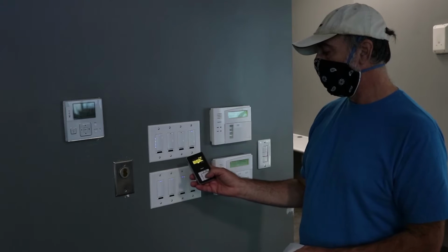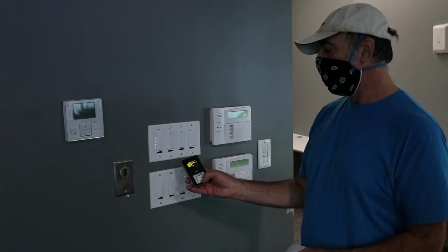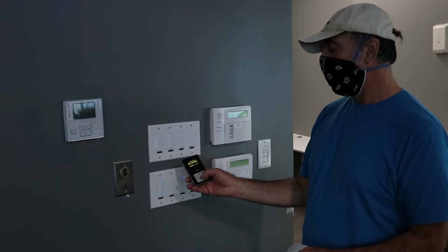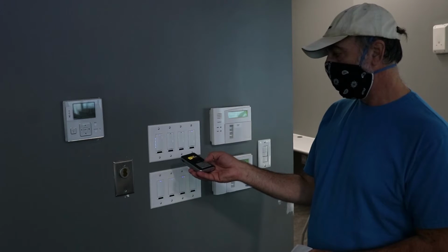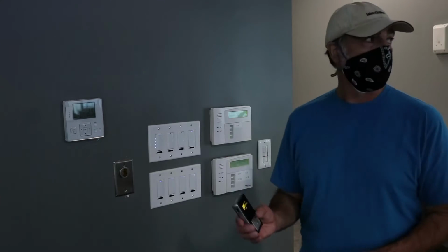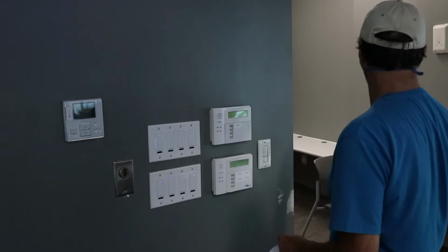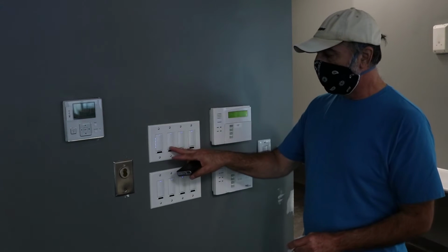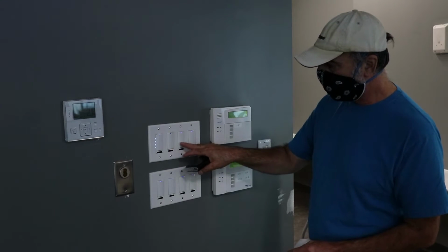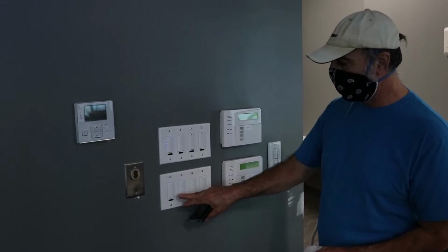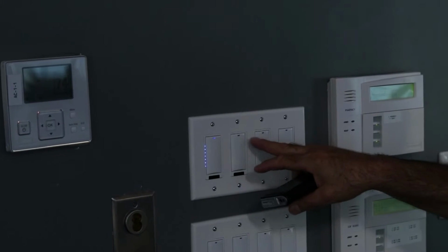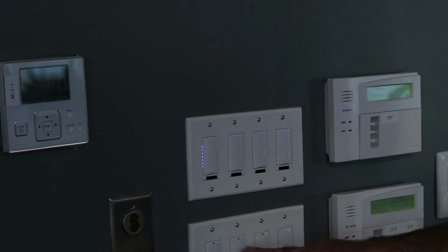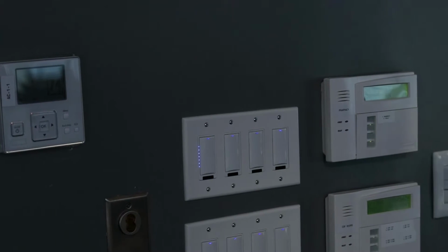So use the remote, go down to the menu to more, go down to utilities, go down to room mode, and then it's already highlighted normal hours, and I want to press normal hours, and the lights I could see throughout the corridors have turned on. The switches are locked out, so the LEDs do turn off, but if I look over my shoulder, I could see none of the lights have actually turned off. Doesn't matter what position you leave them in, I'm just leaving them the way they were.